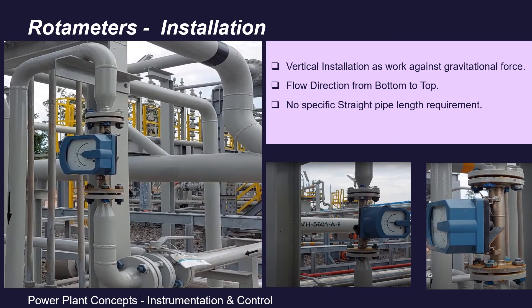Coming to installation: key points to remember are — first, it shall be installed vertically. Second, flow direction is from bottom to top. Regarding straight length requirement, theoretically there is no pipe straight length requirement for rotameters, but it is still advisable to give some minimum straight length before the flow enters the rotameter to get laminar flow.